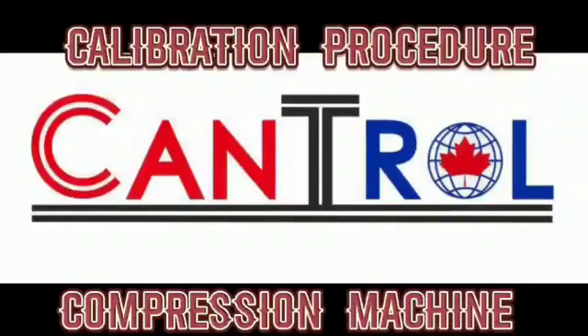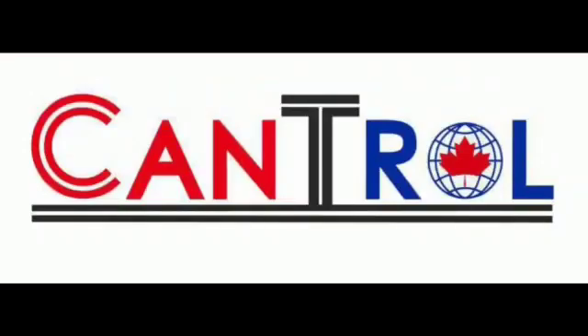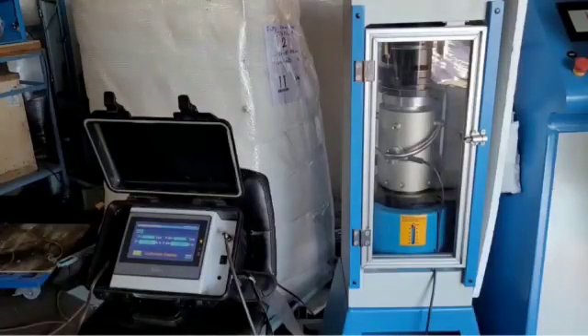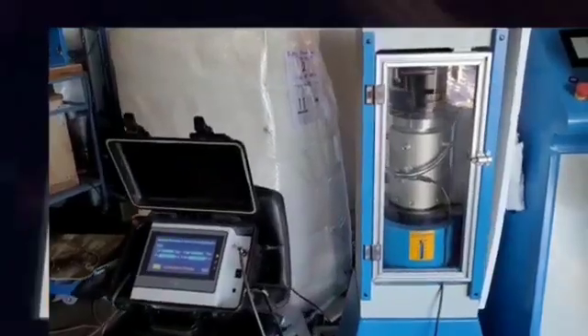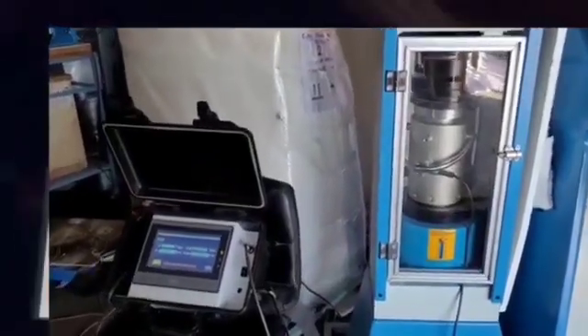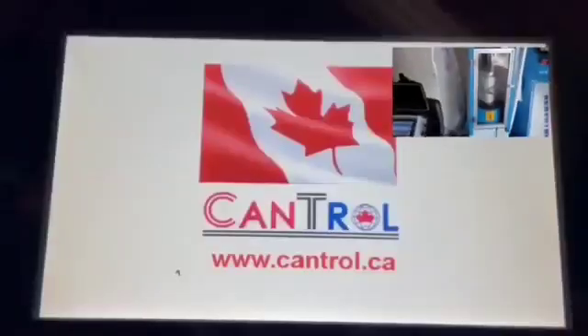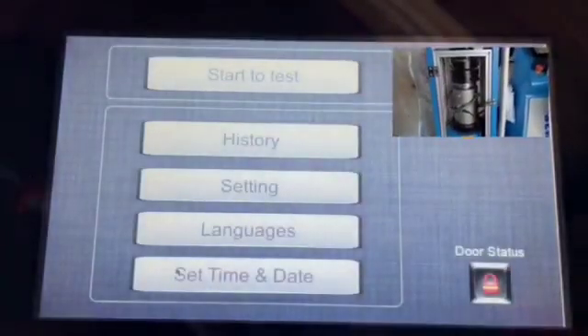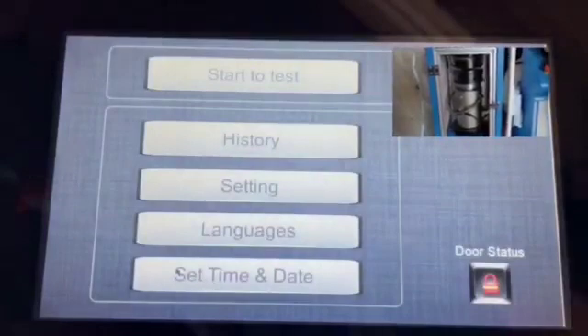Hi, in this video I'm going to show you how to calibrate Cantrol's concrete compression machine. First we put the load cell in the frame and turn on the calibration display. Then we go to the compression machine and turn it on.